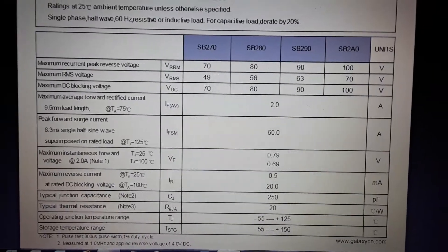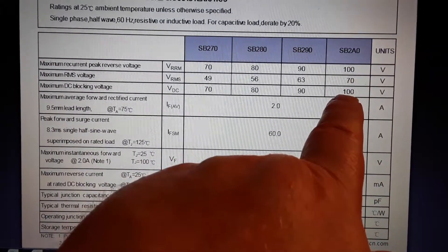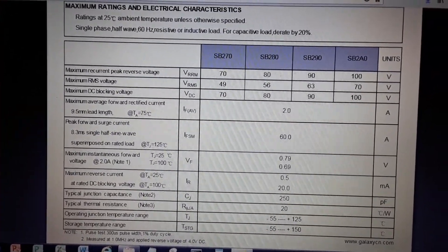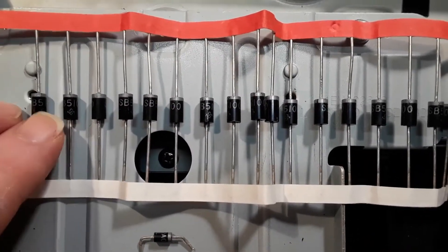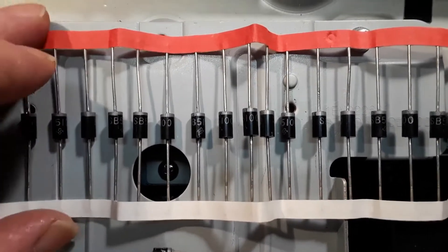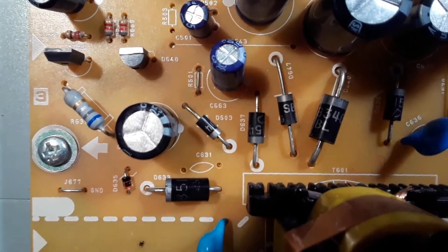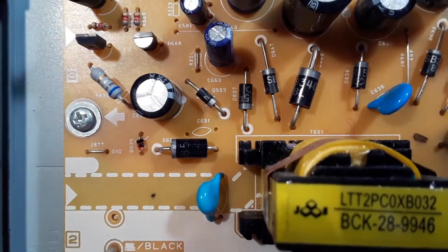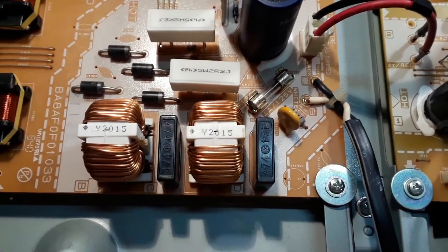It is in fact a barrier diode, and it looks like it's rated at about 100 volts and two amps — the SB2A0, 100 volts and two amps. I think I have an equivalent to that I can install and try. In amongst my parts I found some barrier diodes — these are SB5100, and they're higher rated but they should work fine. I've replaced D633 with the SB5100.